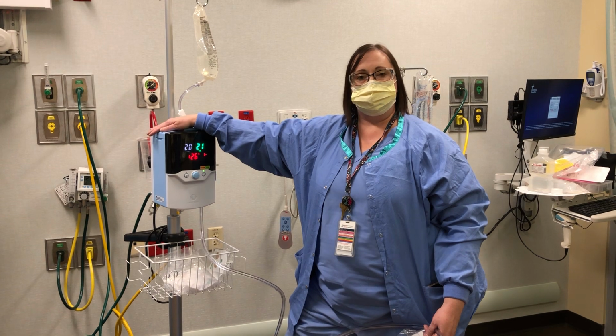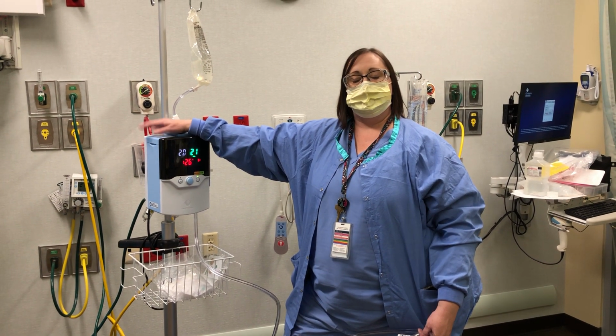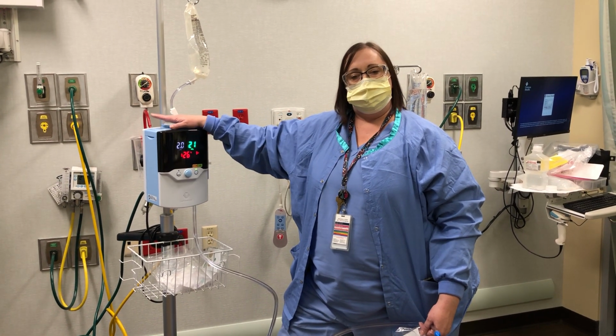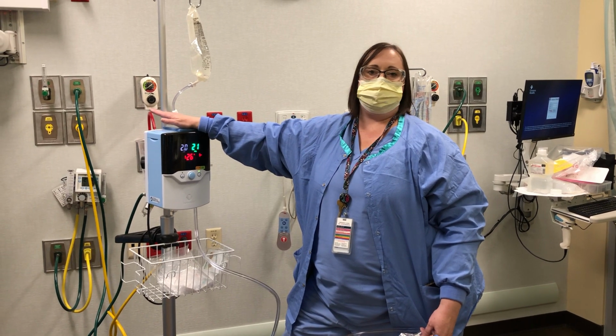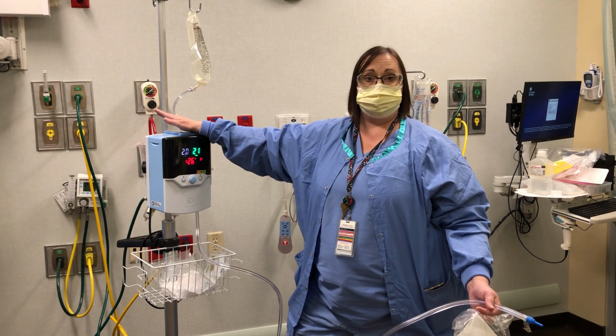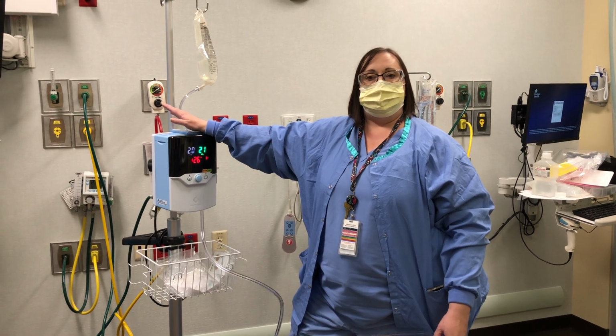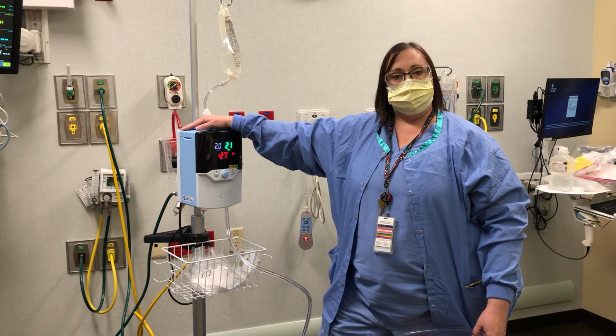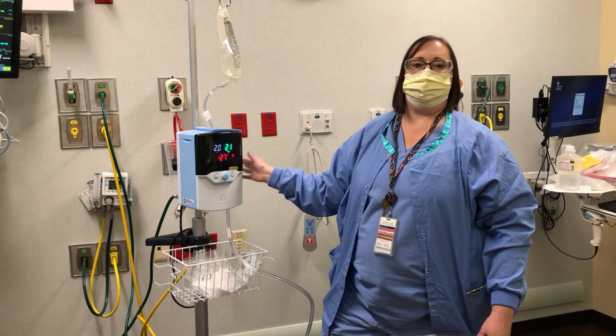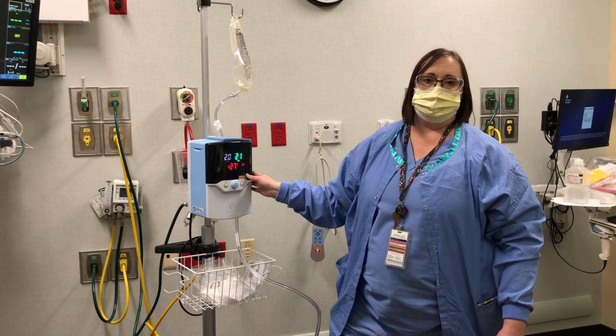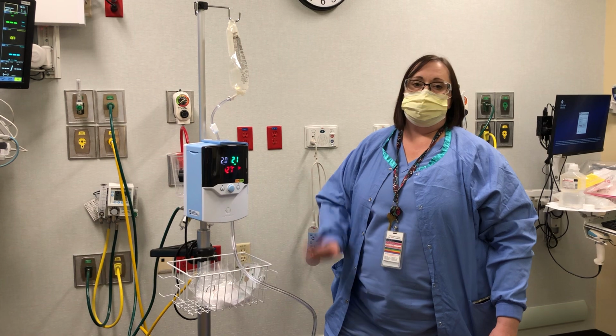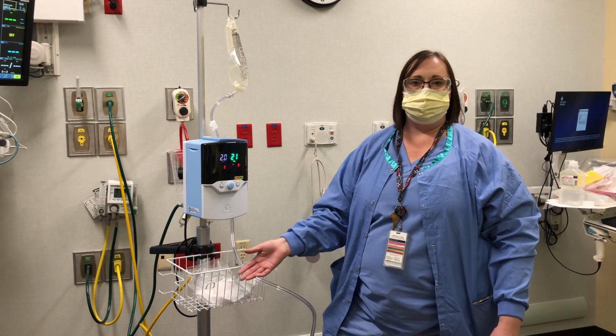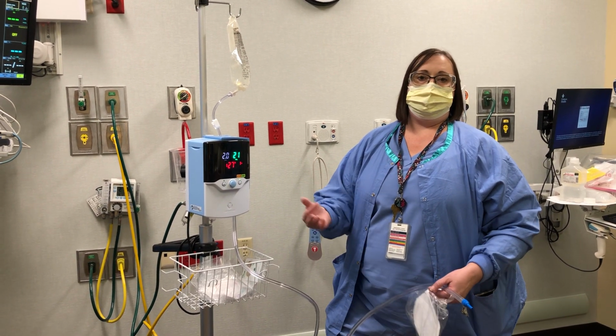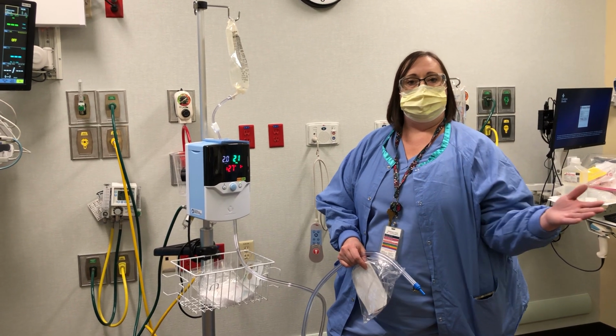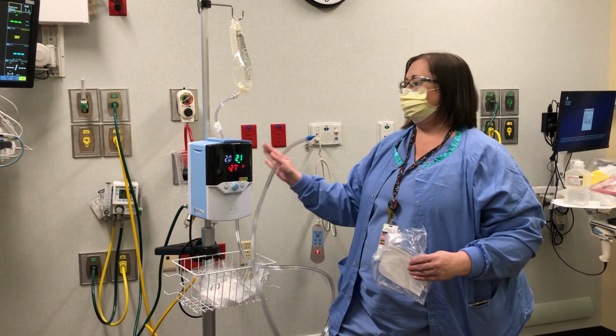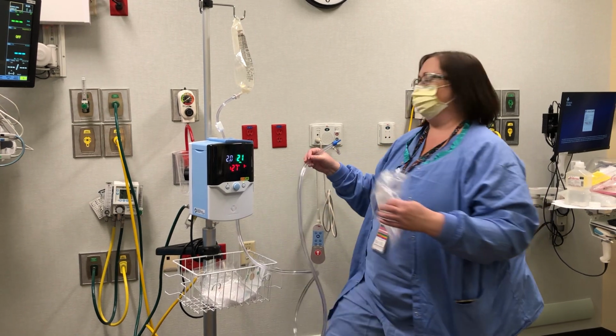We usually try to go to 1 liter instead of 1.5. Again, that is because you're going from a heated and humidified device to just straight air with a little bit of a bubble passover device for humidity. And the baby sometimes will get a dry nose and get bloody, and so it's not as successful, and then we have to go back to the Vapotherm. So we generally don't do 1.5. We do it if we have a baby who's a chronic BPD baby who we're having trouble weaning and we just can't get there, and the 2 to the 1 is just too big of a jump. But generally we stick to 2 and then we'll go down to 1 liter.